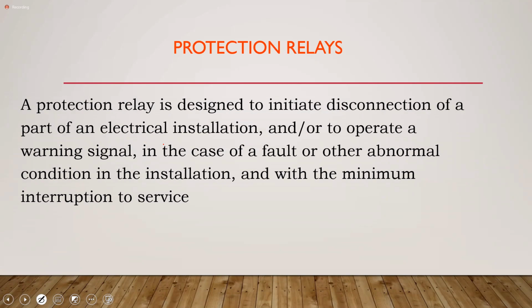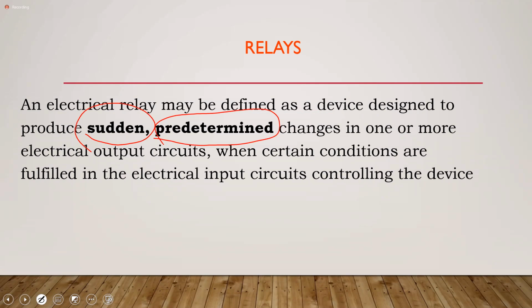Now for your protection relay. Why is it that it doesn't just operate at one standard quick speed? Because we're trying to minimize the amount of time before the fault could spread. So why not have a very quick time for every speed? All right, that's a very, very good question. However, think about it this way. The fact that a current has gone beyond a predetermined value does not necessarily mean that there is a condition that requires system separation. Okay, sir.